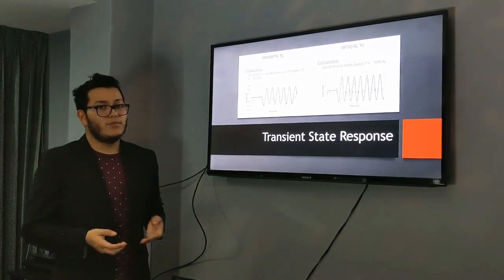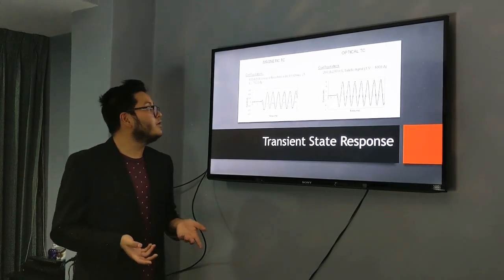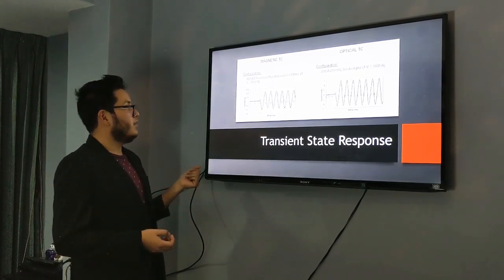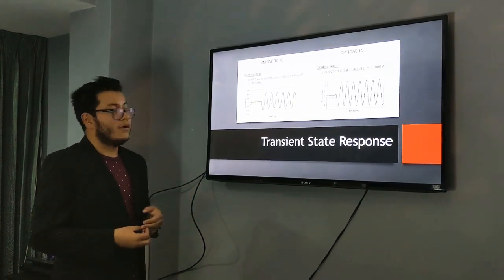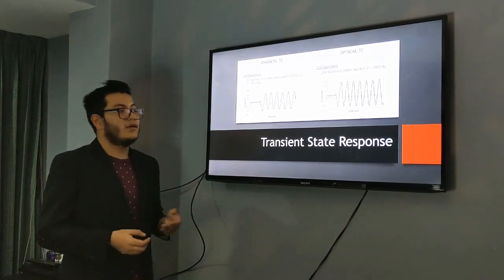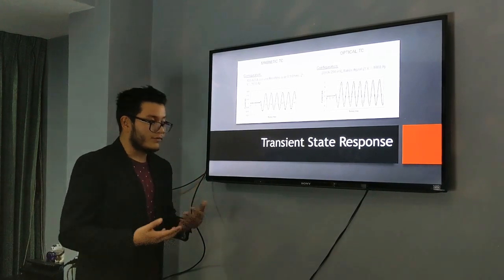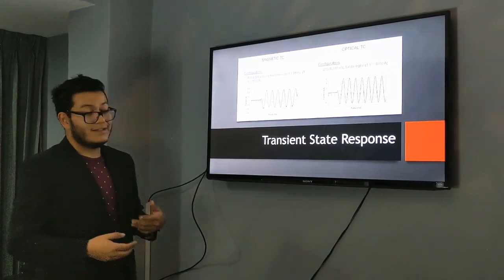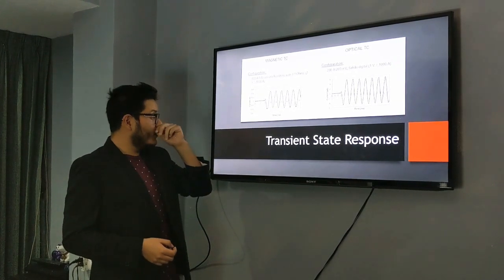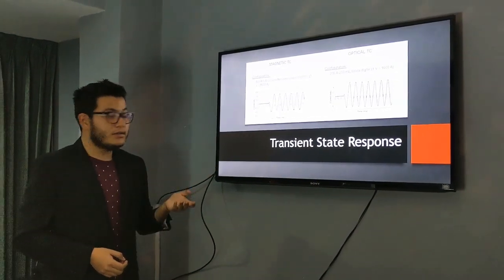The next test we found was a transient state response. Again, both current transformers were put in the same configuration, and the configuration was the same as the last test. In this case, we inject a current reaching the limits of the configuration, so we can see how the sensor of the current transformer behaves against this response. As we can see in both graphs, there's a huge difference between these two. The first one, we can see that the current only reaches 600 amperes against almost 6,000 amperes.